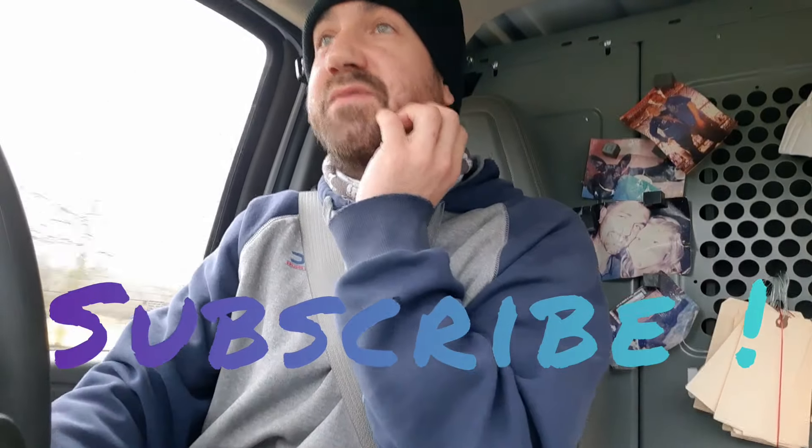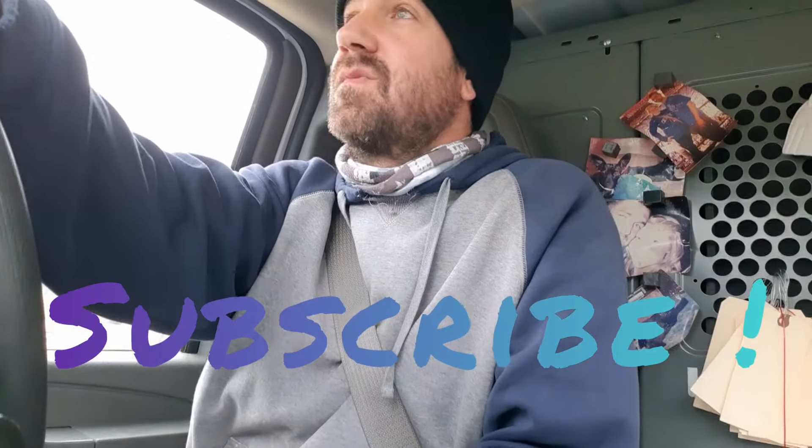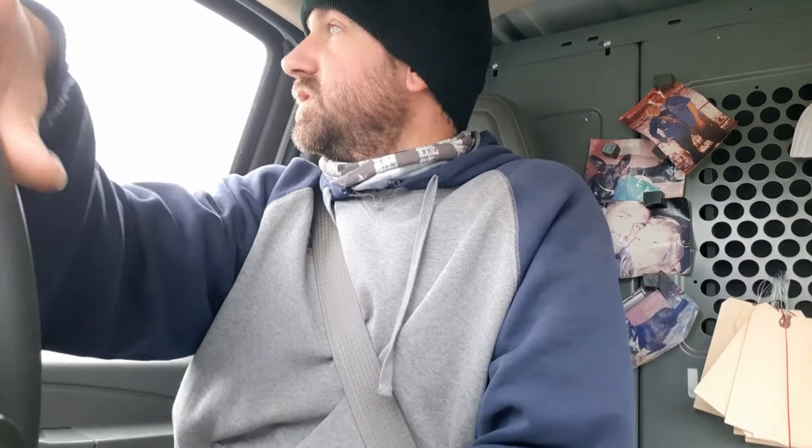We're on our way to the next one. This is the stuff you guys don't see — I've got to drive across town and reset some steam humidifiers that are just gonna lock out again. We need humidity and we've been telling them for months we've got to change the canisters, but the canisters are all delayed. So we're going out there every week, couple times, to reset the humidifiers. Going to reset some power and make sure things come back on.